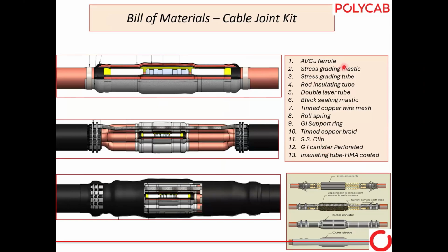So we see aluminum or copper ferrule, stress grading mastics, stress grading tubes, red insulating tubes, double layer tubes, and black sealing mastics, which we use so that ingress of water should not happen from that point. Tin copper wire mesh we use, as a copper mesh is there in the cables. Roll springs are there. These are the basic components, sub kits. We always call them sub kits. And over that, last is an insulating tube.